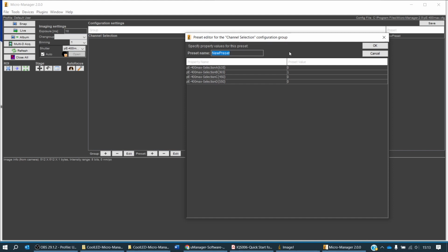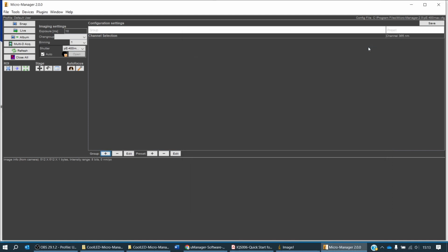Now it's time to set up the presets. You do this one by one, and you start on the 365, which is already switched to 1, and call this channel 365 nanometers. Click OK.